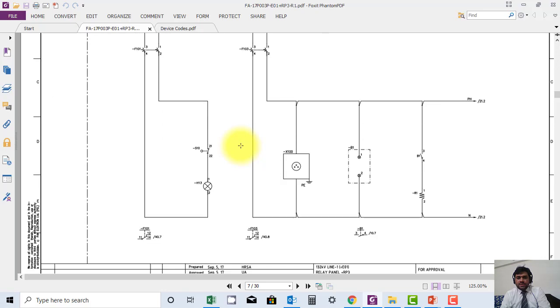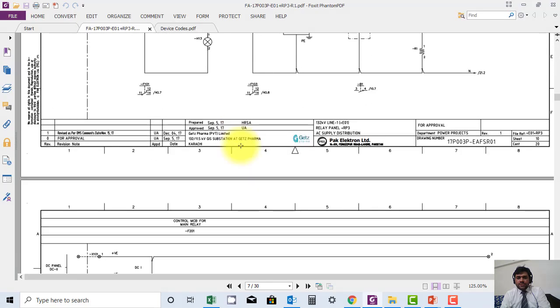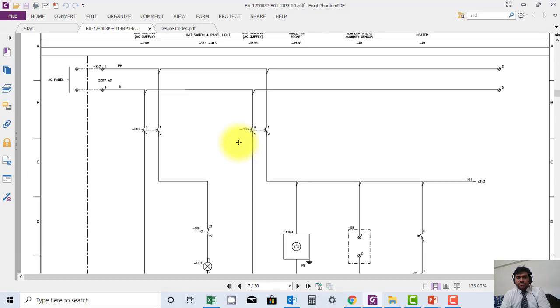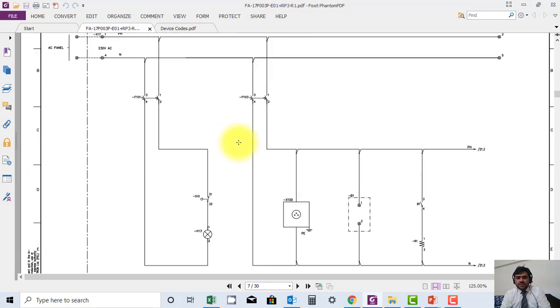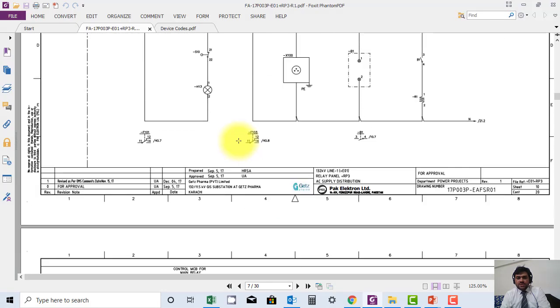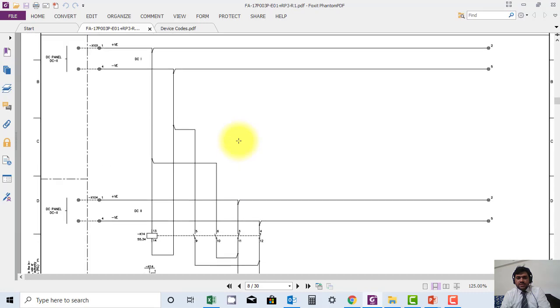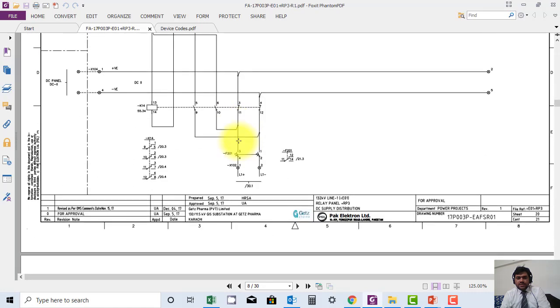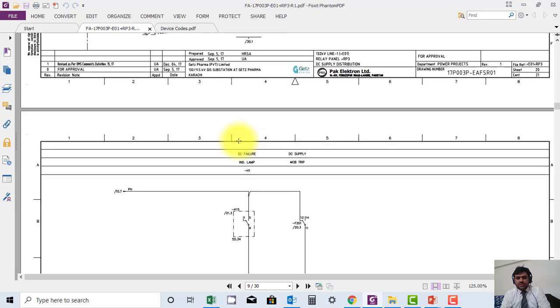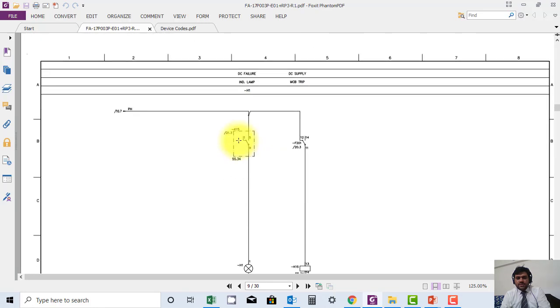Check if there is any mixing between AC and DC loops. Another important thing: inside the panel, DC wiring and AC wiring should be separated and should have separate entrances.